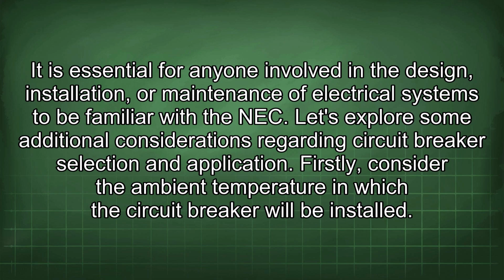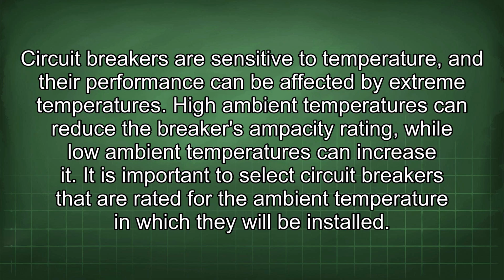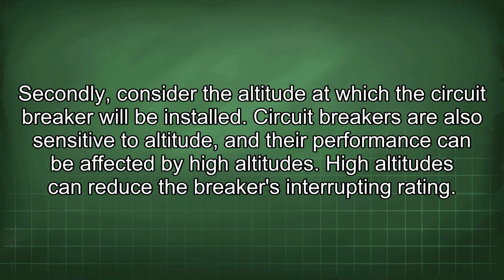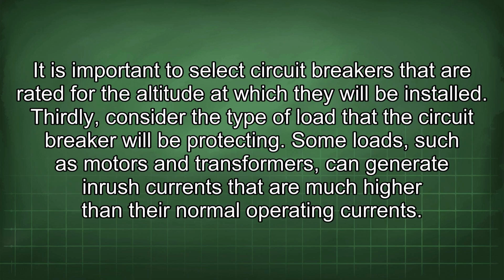Firstly, consider the ambient temperature in which the circuit breaker will be installed. Circuit breakers are sensitive to temperature, and their performance can be affected by extreme temperatures. High ambient temperatures can reduce the breaker's ampacity rating, while low ambient temperatures can increase it. It is important to select circuit breakers that are rated for the ambient temperature in which they will be installed. Secondly, consider the altitude at which the circuit breaker will be installed. Circuit breakers are also sensitive to altitude, and their performance can be affected by high altitudes. High altitudes can reduce the breaker's interrupting rating. It is important to select circuit breakers that are rated for the altitude at which they will be installed.